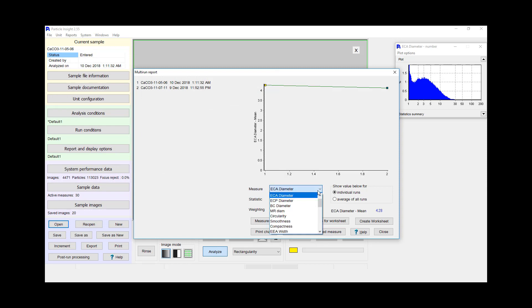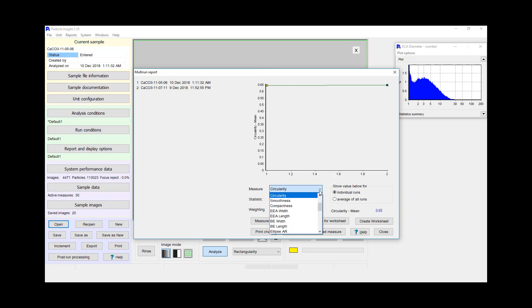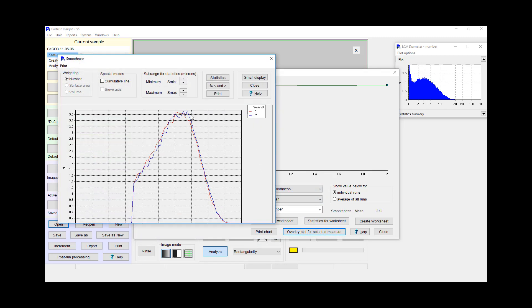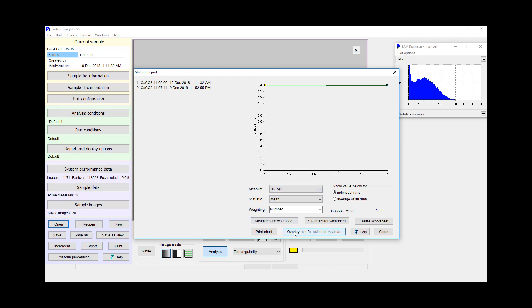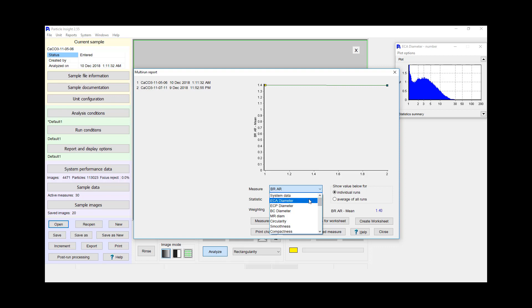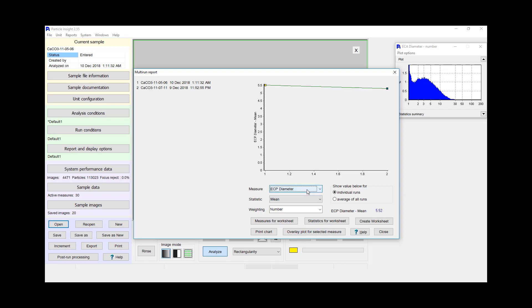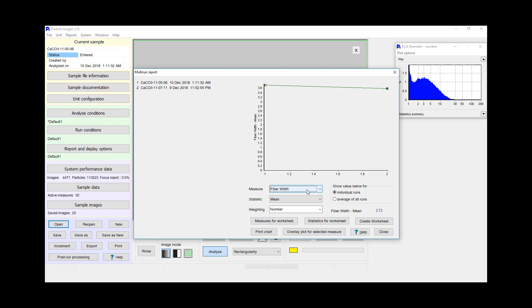I'll do an overlay not just of size — which seemed to be very, very similar — but let's look at the shape differences. We can look at circularity, for example, to see if they were different in roundness. They're both pretty round, equally round — one being very round. So both samples are very, very similar. We could look at smoothness as well — a slight more smoothness in the blue sample. Looking at aspect ratio, that really shows no difference. So these two samples would be very similar. The benefit here is that you can do an overlay of size plus all different types of measurements: perimeter diameters, bounding circle diameters, mean radius, circularity, smoothness, compactness.